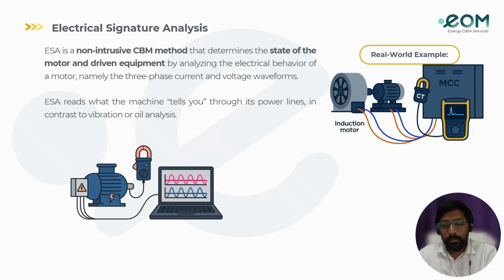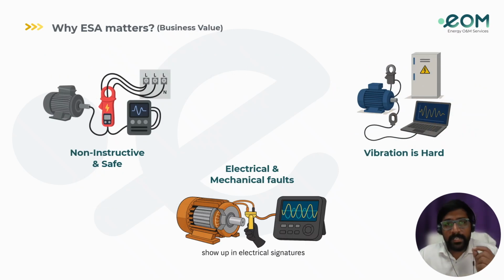So let's move on and discuss why ESA matters in terms of business value. First thing, it's a non-intrusive and safe method. Clamp at the MCC, so no open bearing housing or coupling guards are needed. The second one is that it covers both electrical and mechanical faults: rotor bars, stator faults and bearings, misalignments, and even load issues, which show up in the electrical signature as well.